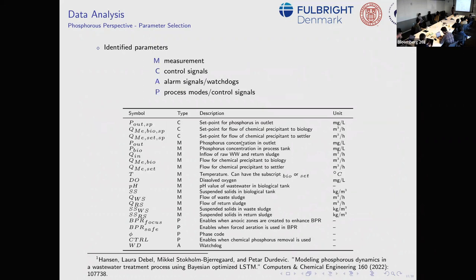Here's one of the papers where we tried to model a system using LSTM. These are the parameters we identified — very important parameters are of course phosphorus, because that's what we're trying to control for, but also the flow in, which is a disturbance, temperature, dissolved oxygen, pH, and suspended solids — all influencing the biology: food, oxygen, and pH affecting the bacteria.